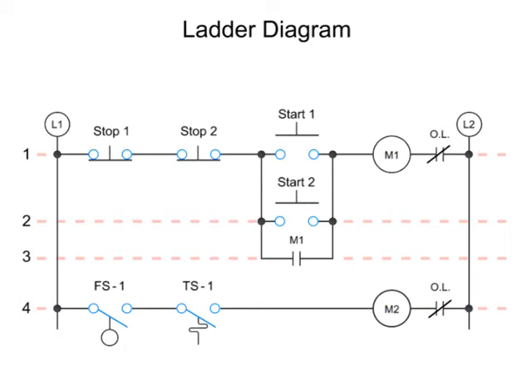When referencing wire segments associated with each rung, you start at the top left and number every wire between contacts. You would number the wire against rail L1 and the stop 1 contact as wire 1, the wire between stop 1 and the stop 2 contact as wire 2, and so on across the circuit, with each subsequent wire between contacts numbered sequentially.